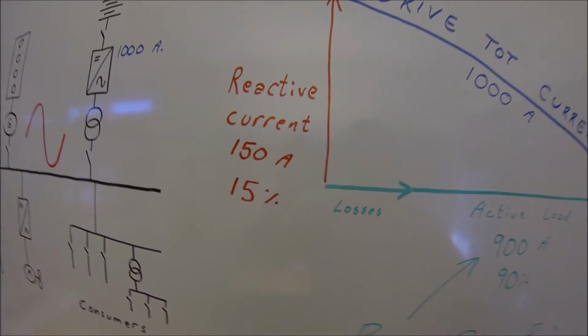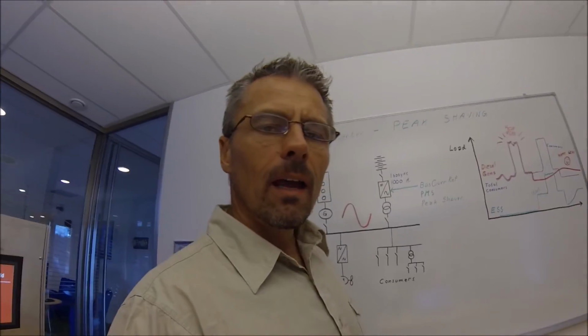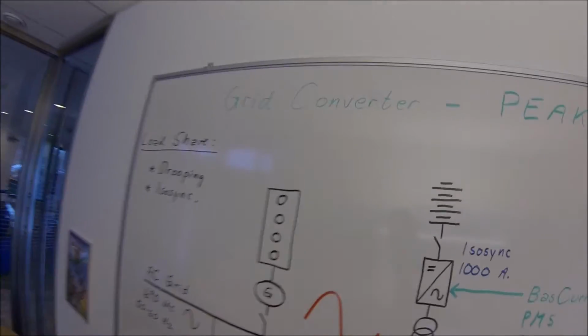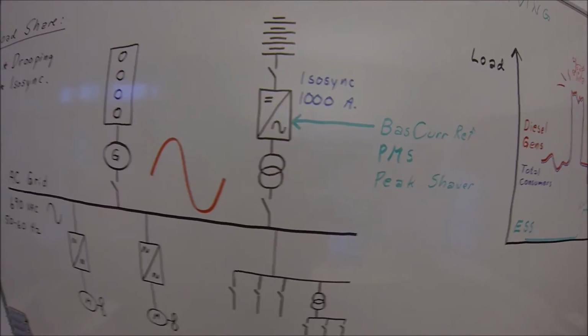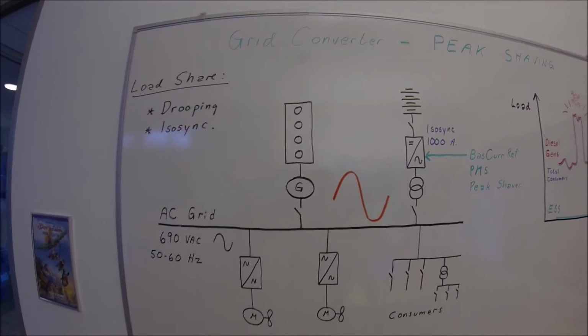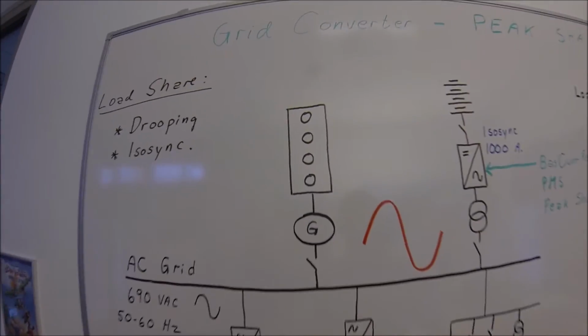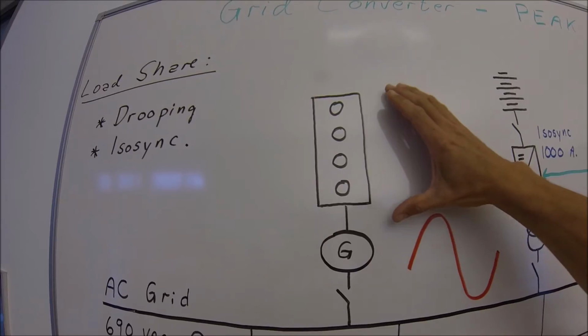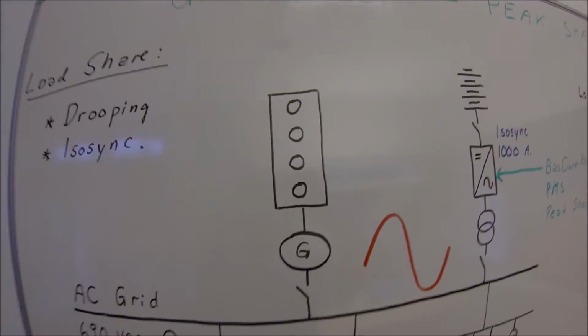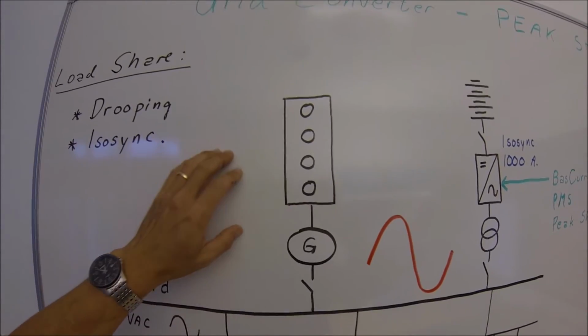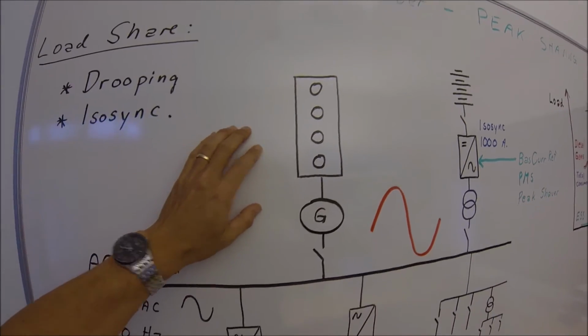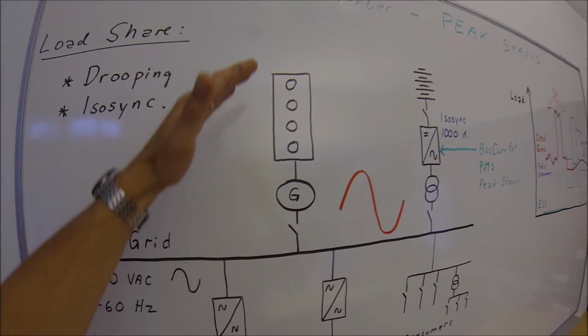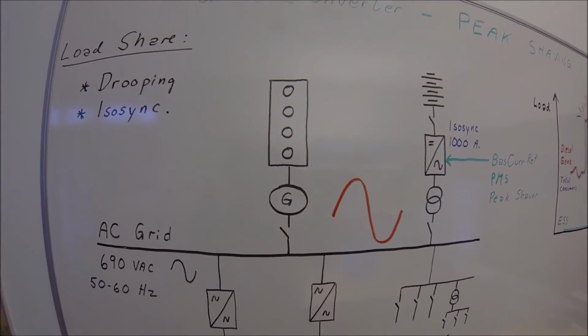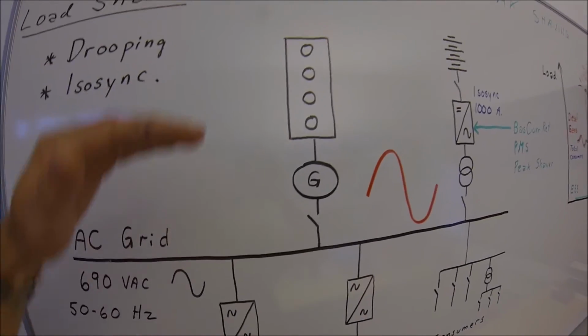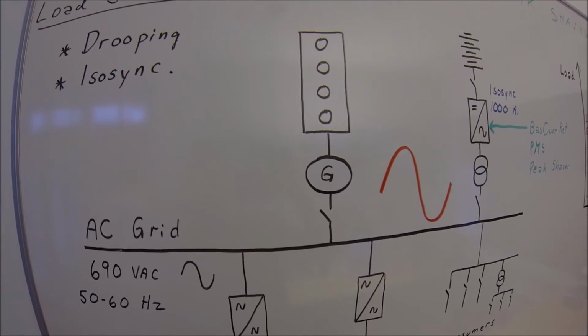Now let's take a look at peak shaving. Energy storage is used to a great extent for peak shaving. When is the peak shaving needed? That is to reduce the dynamic load on generators, especially liquid natural gas generators. They have very slow dynamic characteristics. The performance is not too good for big changes in load.